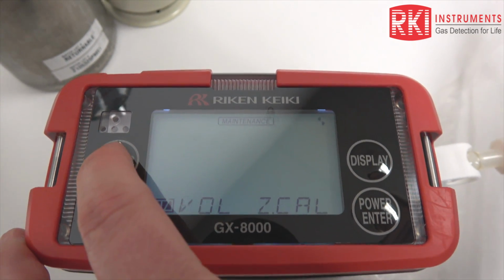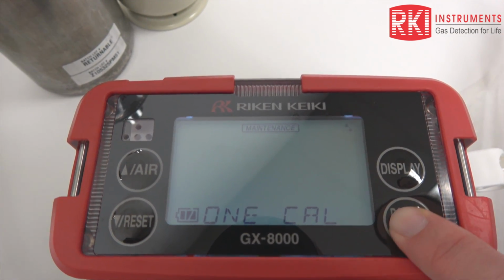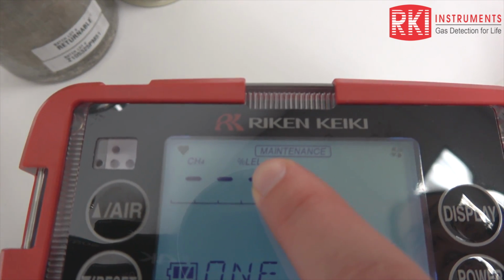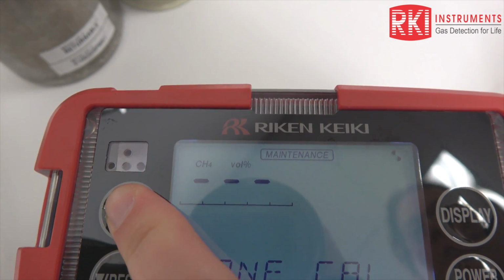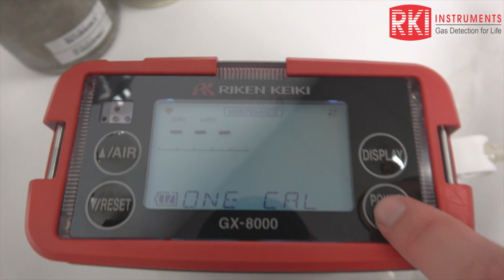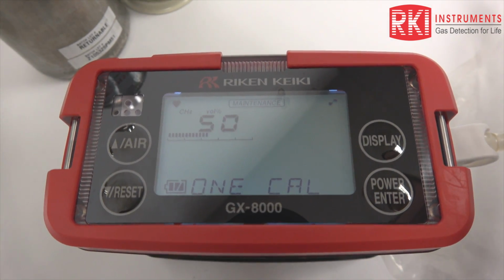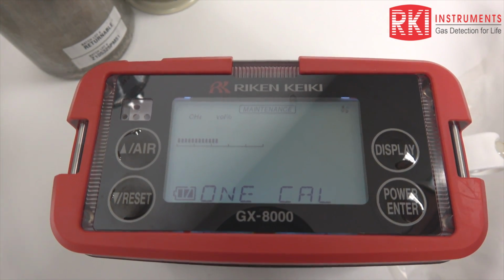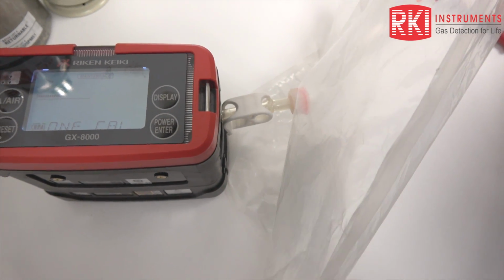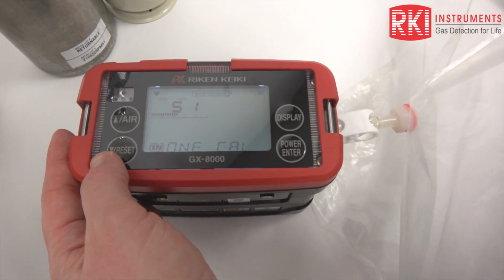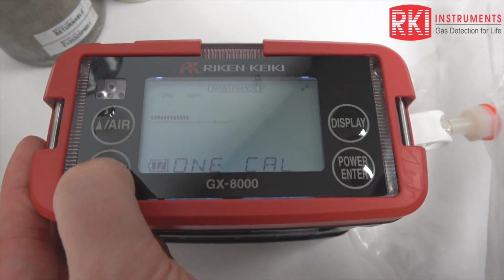So I need to get back into my 1 cal. This is the LEL combustible. You can see the percent LEL here. Just press air to get to the volume combustible. So I'm drawing from my bag already, and it says 51. Again, I'm using 50%, so I need to bring it down.